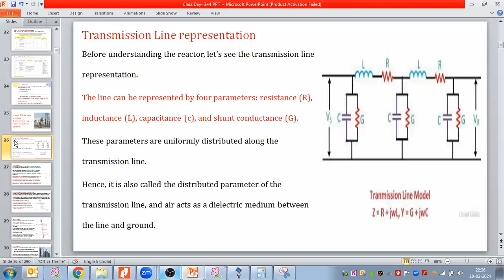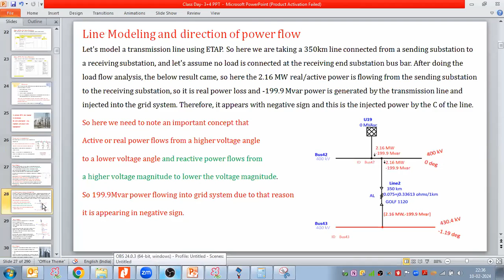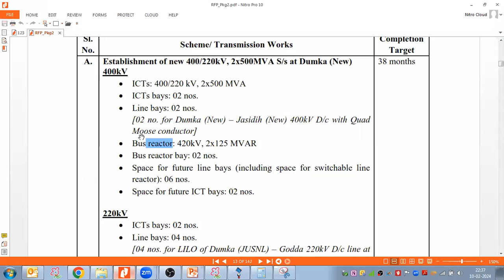Coming back to the discussion of why the reactor has been used. So anyway, so far I'm clear why reactor is used here. The reactor is used to compensate, because here we have a longer line length, two number lines, and both lines could be of longer line length, so to compensate the capacitive reactive power, this particular substation requires the reactor.